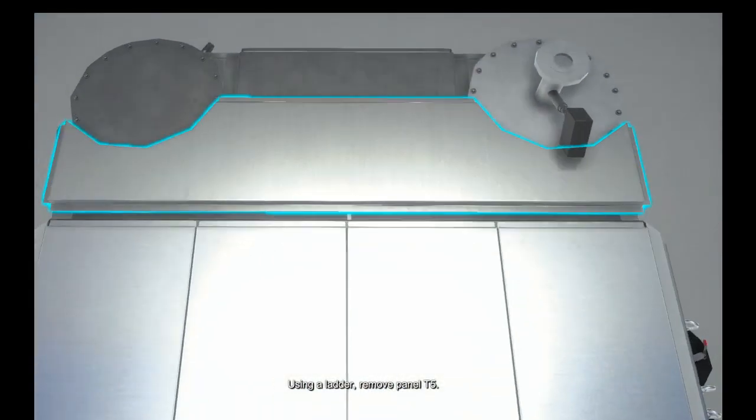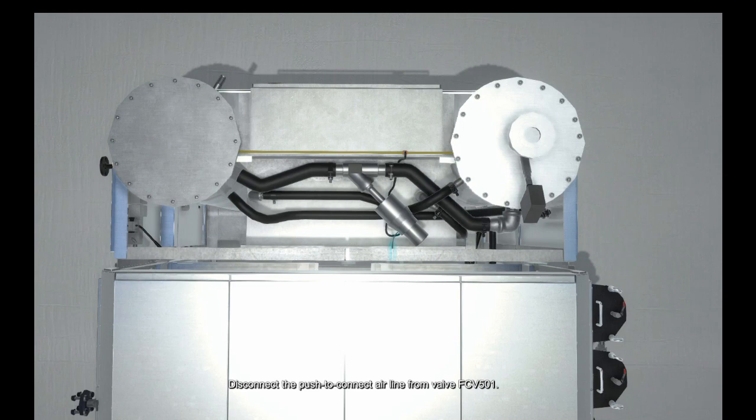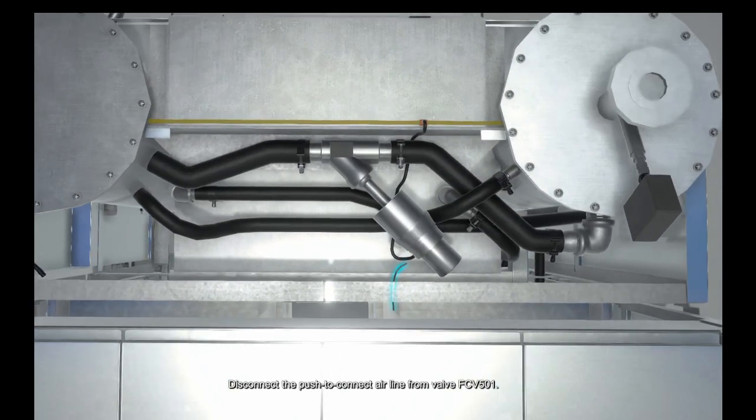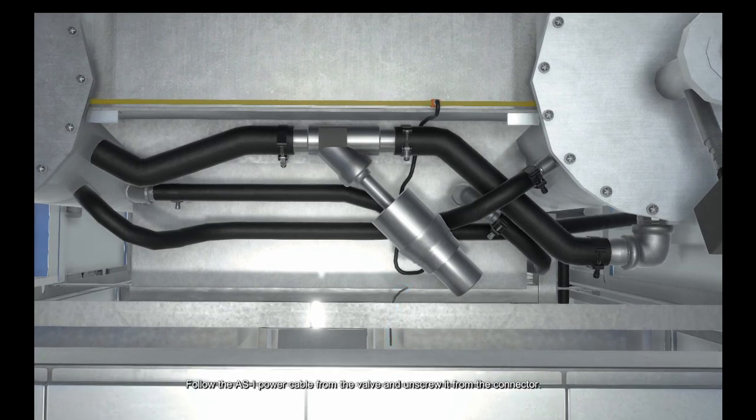Using a ladder, remove panel T5. Disconnect the push-to-connect air line from valve FCV501. Follow the ASI power cable from the valve and unscrew it from the connector.